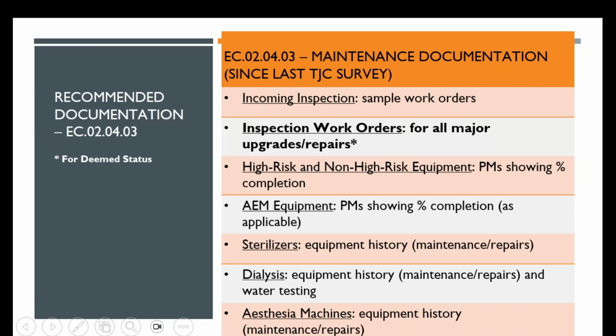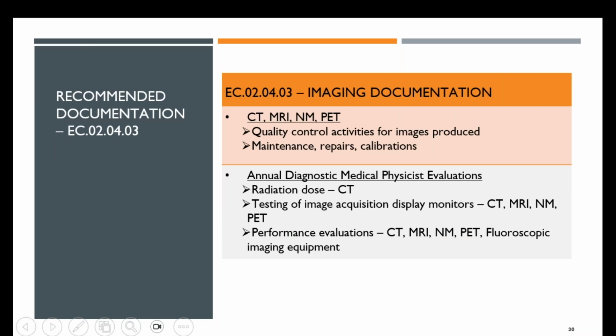And the last piece of information or documentation for the standard is the imaging, which you should have from the last Joint Commission inspection or the last 3 years. This includes the quality control activities for maintaining the quality of CT, MR, nuclear, and PET, as well as records of maintenance, repairs or calibrations performed, as well as having those annual diagnostic medical physicist reports that we spoke to earlier. And especially for CT, they need to test the radiation dose.